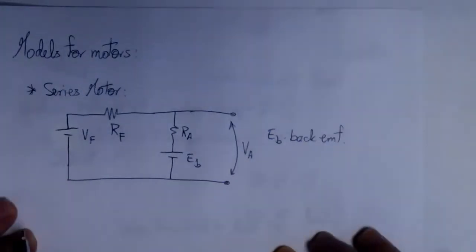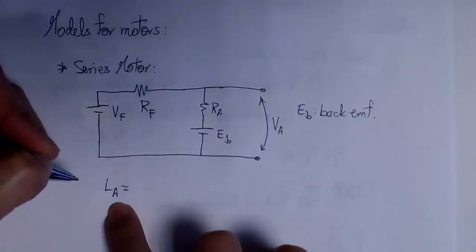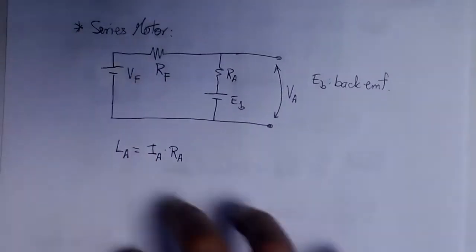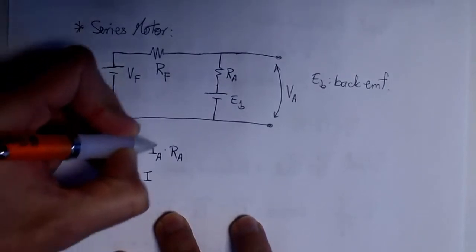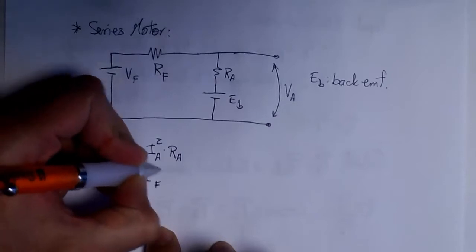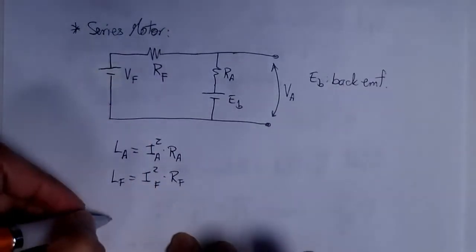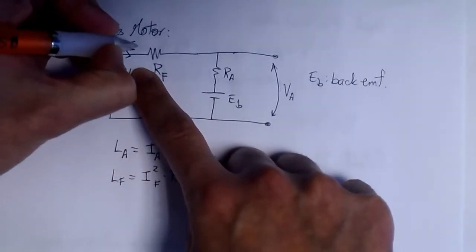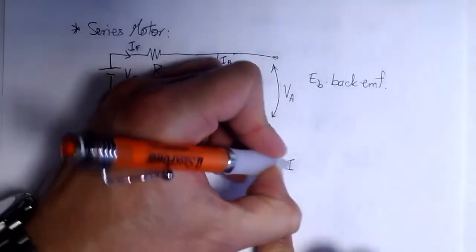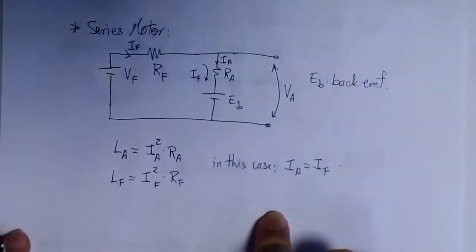We also have the total voltage in the armature windings, and EB is the back EMF. With this model it's easy to compute losses. Losses in the armature windings are given by IA² × RA, and losses in the field windings are IF² × RF. In a series motor, the same current flows through both the field windings and the armature windings because they are connected in series — so IA equals IF. This is only true for this type of motor.